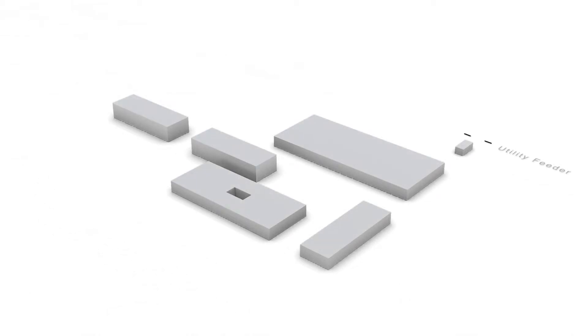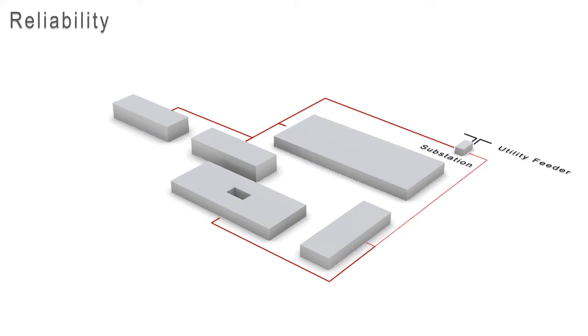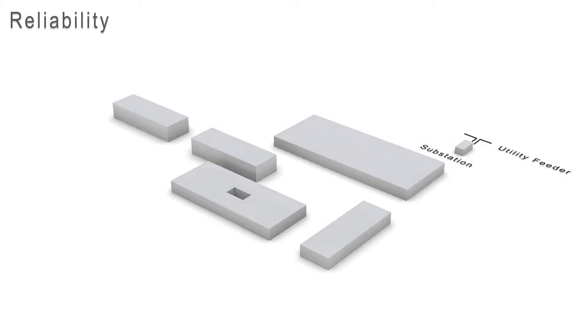First, let's discuss reliability. Here's an example of a radial distribution system. Notice that there is only one path for the electricity to flow from the substation source to each building. If there is a disturbance, then a breaker trips in the substation, and all of the buildings along the distribution line are disconnected from the source, leaving everyone in the dark.